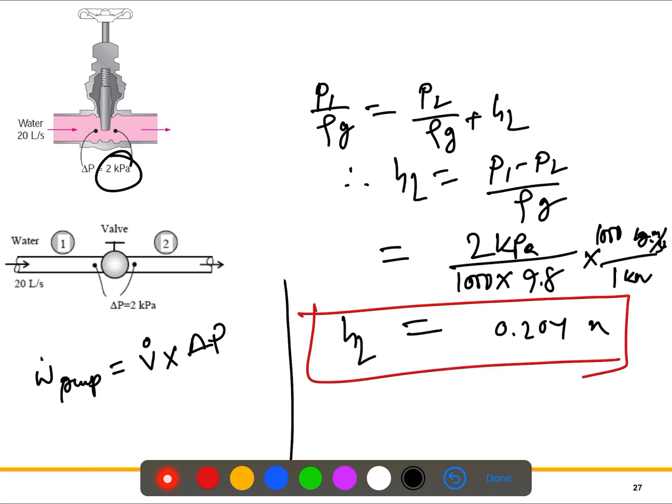The simple formula is the volume flow rate times the pressure difference. The volume flow rate is given here as 20 liters per second, so 20 liters per second we can convert into meters cubed per second. So it will be 0.02 m³/s. Delta P, that's the pressure difference, 2 kPa.